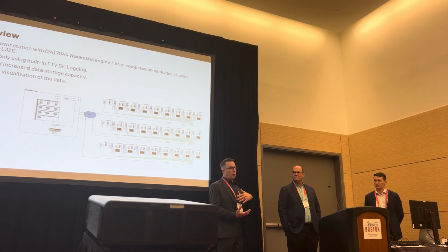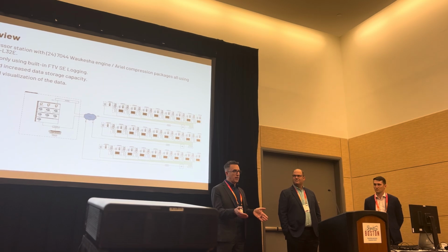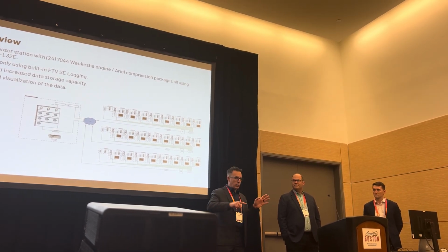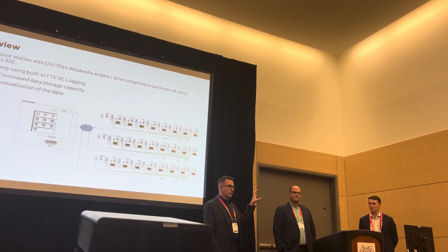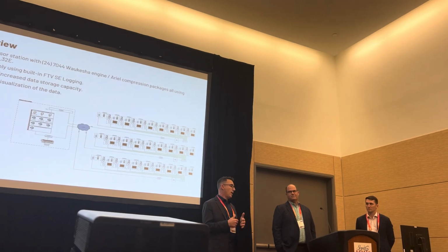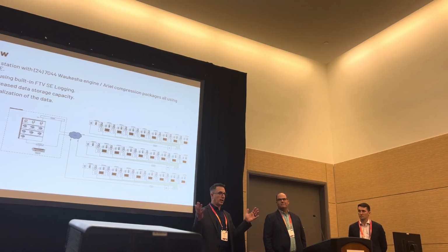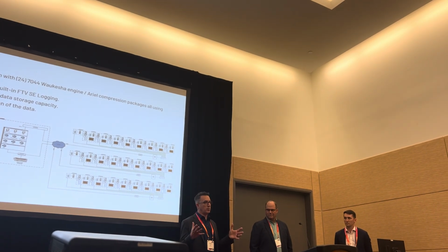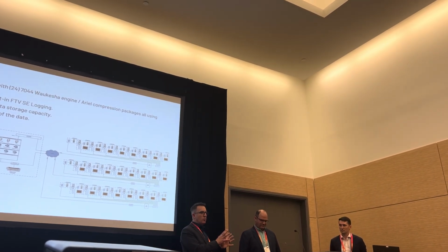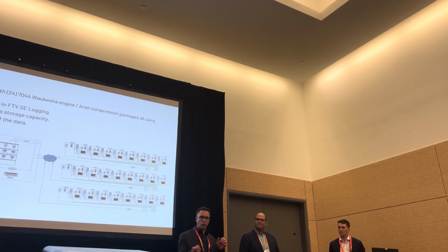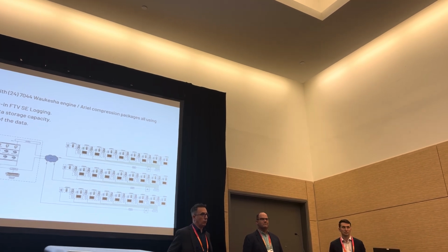But with a camera, for example, you have the capability of saying, I'm looking for a leak, I'm looking for PPE, I'm looking for someone who's on the fence, and you're reporting that by exception. I am not streaming video to a big screen so someone can park there and look at a bunch of video feeds. You want the intelligence to be there and tell you when you need to pay attention to it. That way you can react much faster, and you're not blowing out your communications infrastructure and having to put up more radios and more things. That's a never-ending cycle. So you want to do that heavy lifting with low latency right next to the asset and then report by exception. At least that's what I see a lot with what's occurring right now.